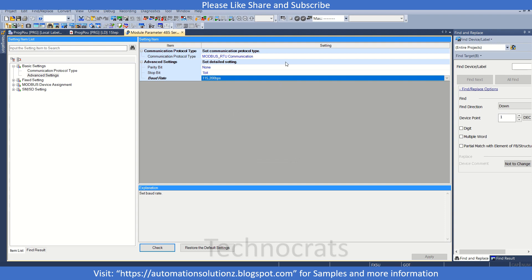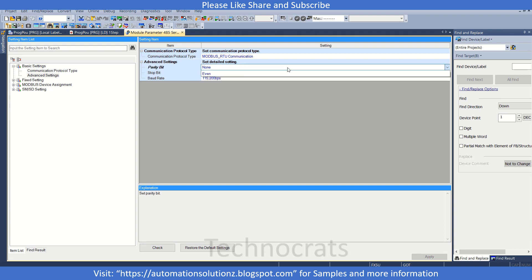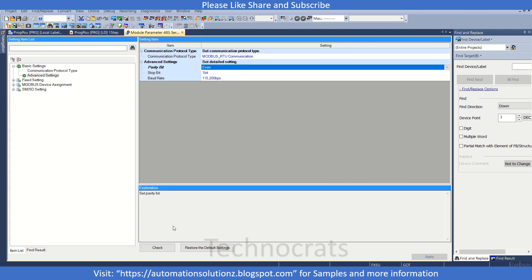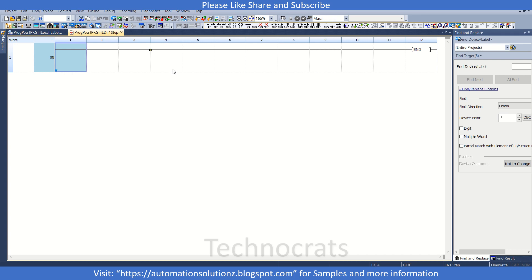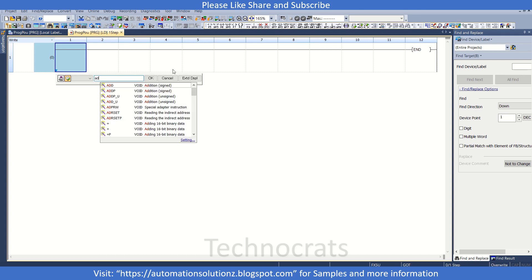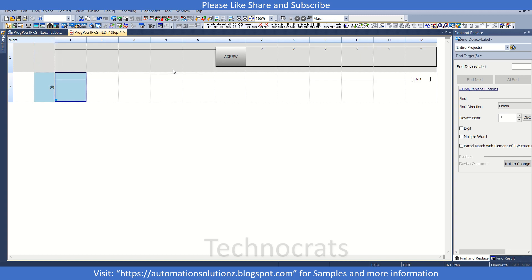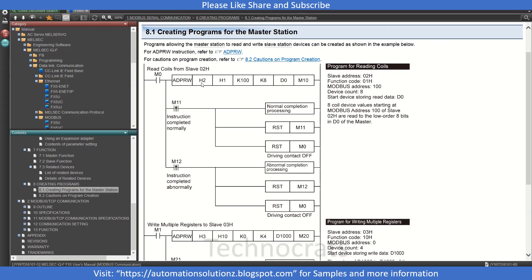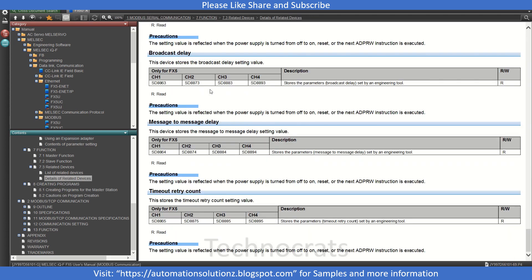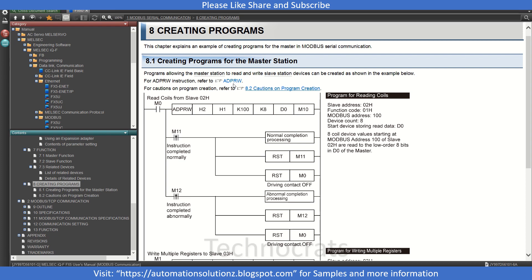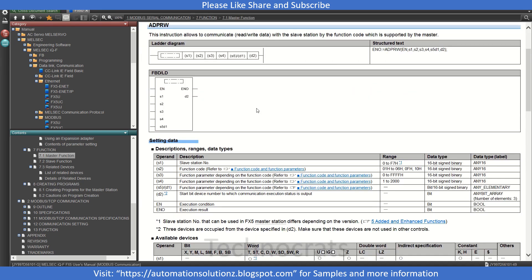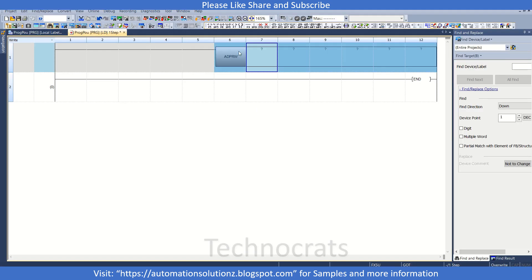So now we can use the ADPRW instruction. Let us first discuss about the instruction points that we have here. Let me open the manual. The first block is H2, means the slave address. So the first point, that is S1, is your slave station number. So let us go to the program and we'll write H1, that is our first station.